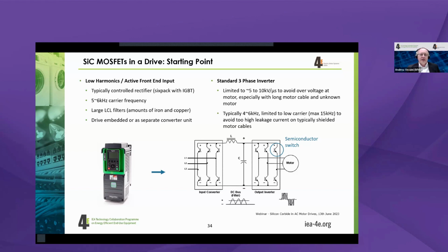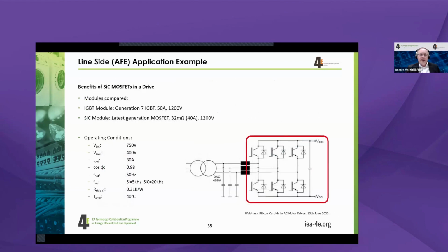Typically, such low harmonics active front-end inputs operate at a carrier frequency of 5 to 6 kilohertz and use additionally large LCL filters for the line side. They're either embedded or as a separate unit. For an example of such an active front end, this is about a 22 kilowatt, so it's 400 volt line-to-line voltage, 30 amps RMS current. In a silicon-based inverter, you would switch with 5 kilohertz, and with a silicon carbide, you would go up to 20 kilohertz. Remember what we saw before, increasing the switching frequency will not have such a big impact on the total losses of the silicon carbide.